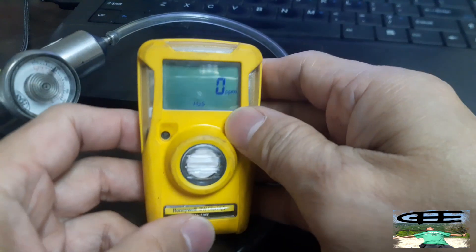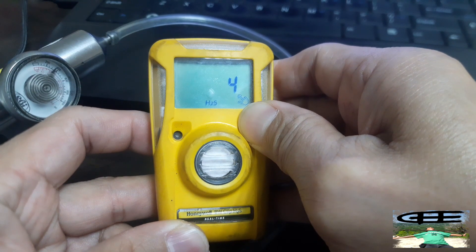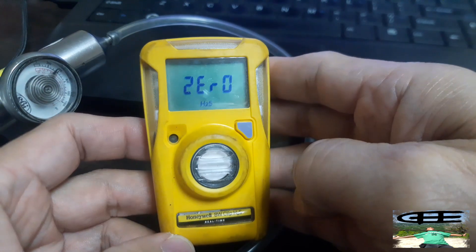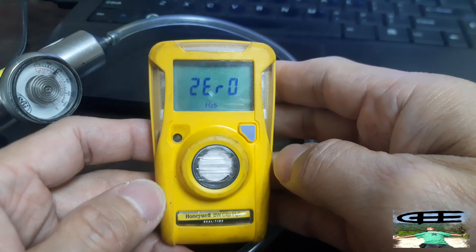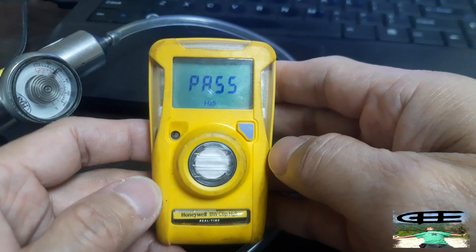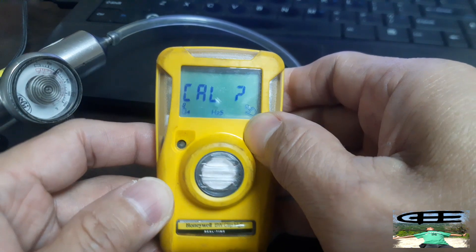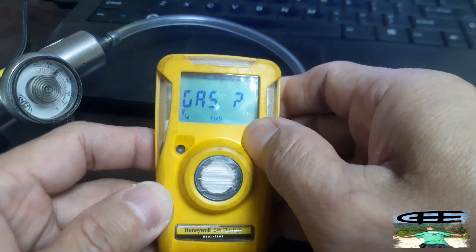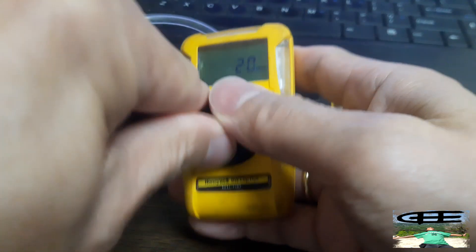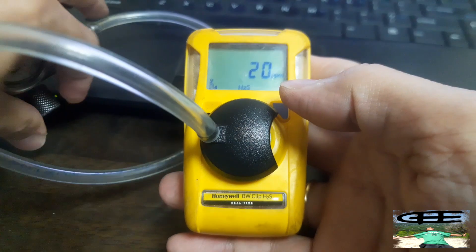Press and hold the button and then there will be a countdown. It's now zeroing. Then CAL accept it, then gas accept it, then apply the gas. We will wait for the countdown until it is finished.